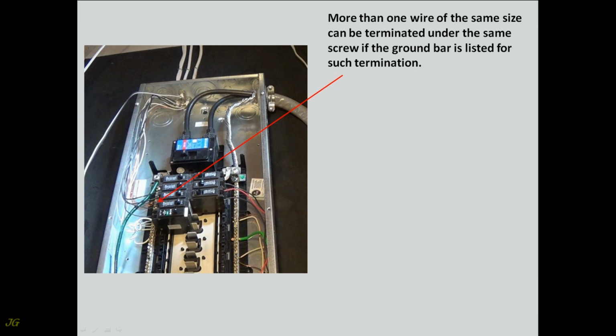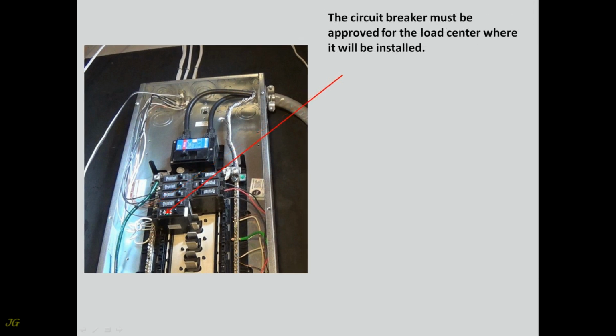More than one wire of the same size can be terminated under the same screw if the ground bar is listed for such termination. The circuit breaker must be approved for the load center where it will be installed.